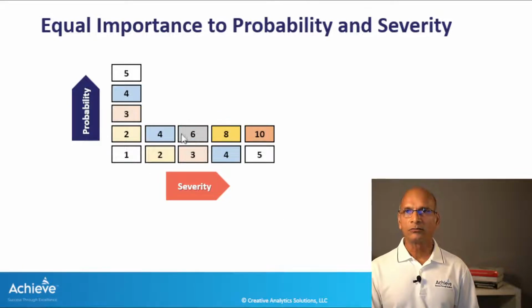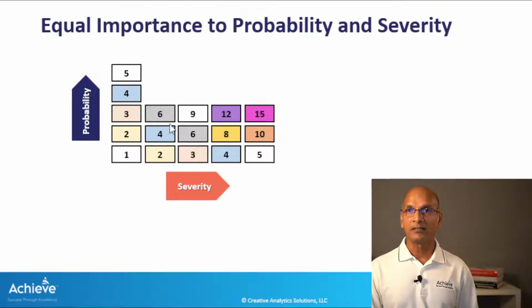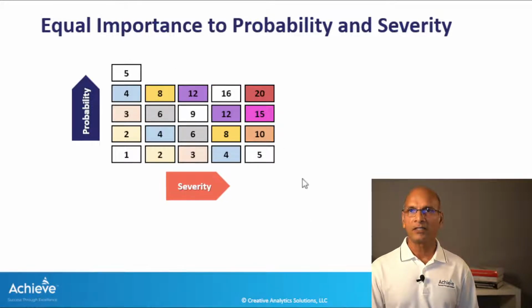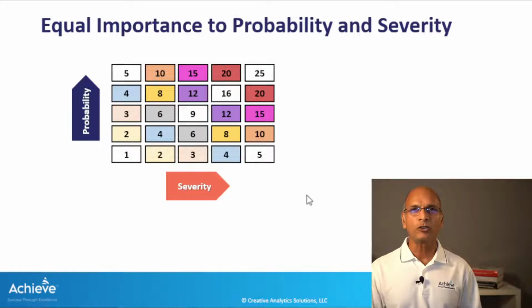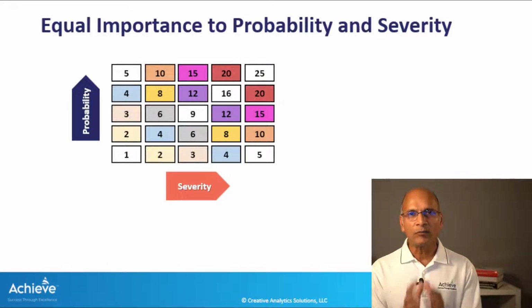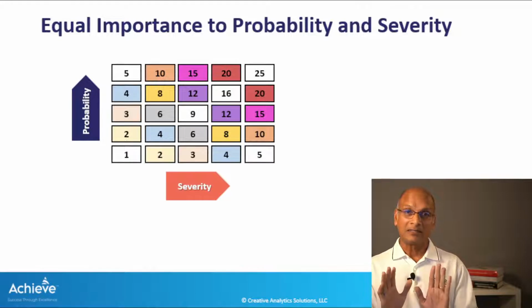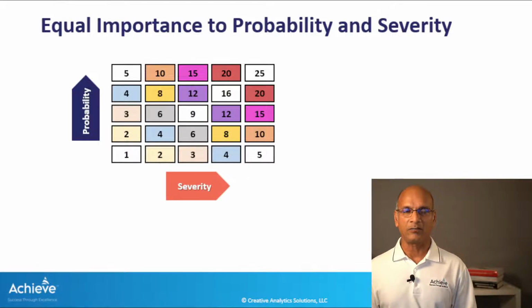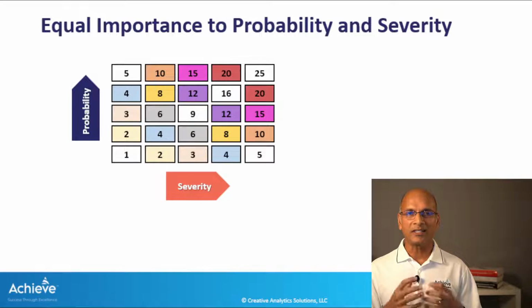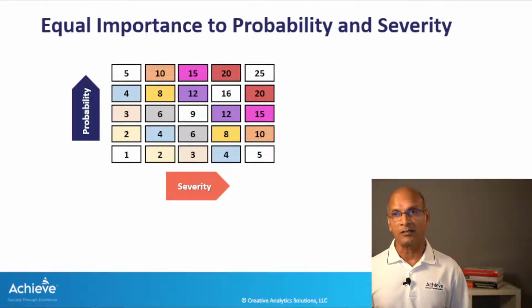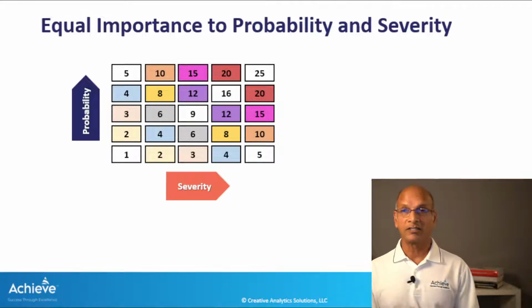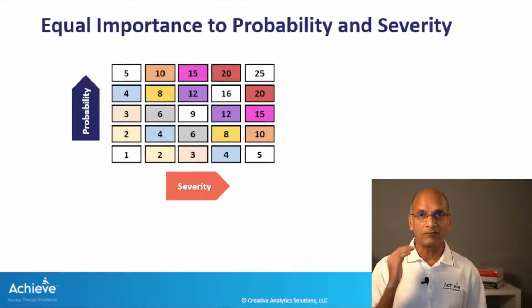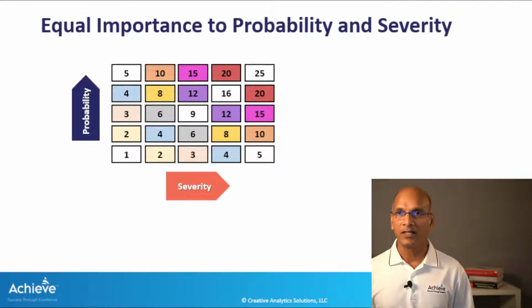When it's 2, you can have 4, 6, 8, and 10 based on different severity levels. Similarly, when the probability level is 3, you get 6, 9, 12, and 15. Then 8, 12, 16, 20, and 10, 15, 20, 25. So you can have all these combinations, right? When you multiply the two numbers, you have a numerical number. Now, it may not mean anything from a mathematical or probability point of view, but it is a reflection of a certain level. And we are not assigning a value judgment to that number. We are not saying this is low, this is medium, this is high. It is just a number. So you are defining or estimating a risk by a number.